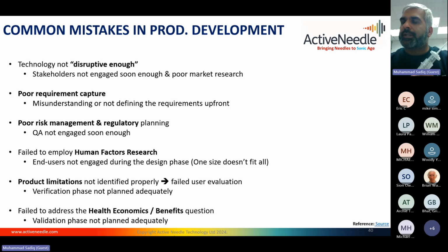We actually had one clinician, a female clinician who had a relatively smaller hand, and she was struggling. She could not even trigger, prime the device, because she could not rest her palm here, as her palm was not big enough to get supported here. So that's something we need to work on in our next generation of devices.